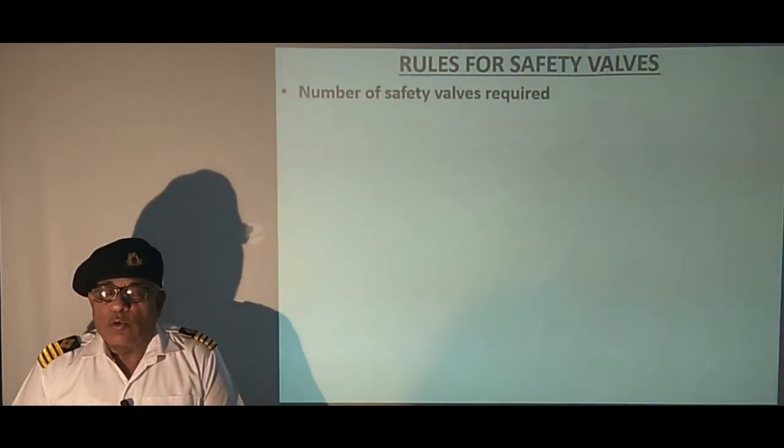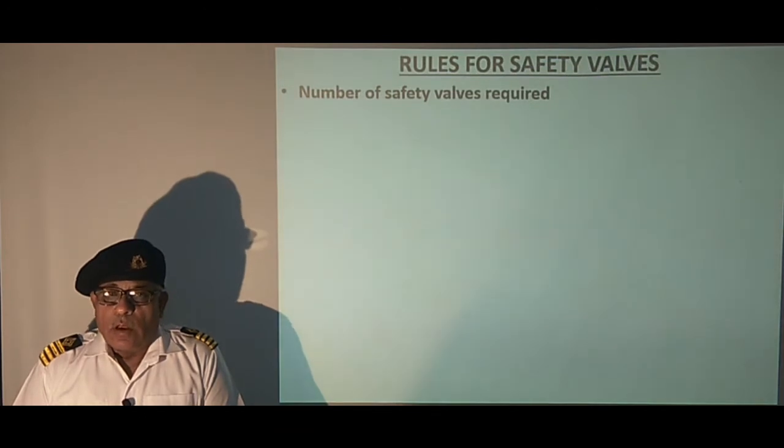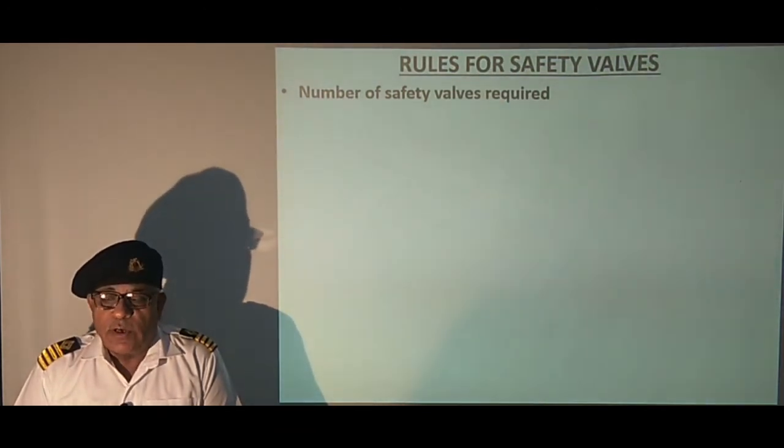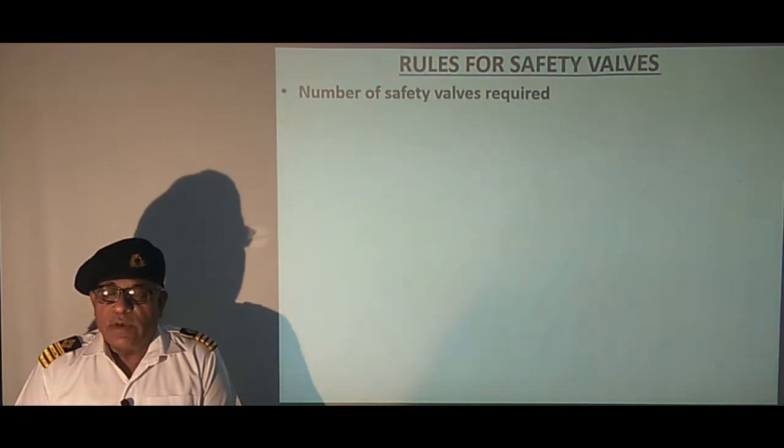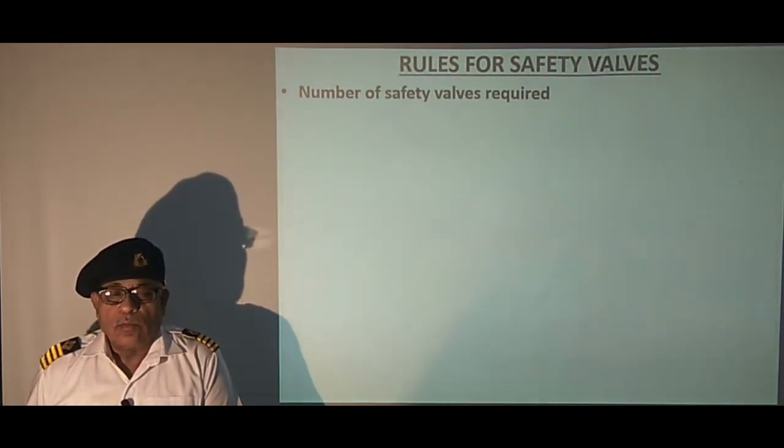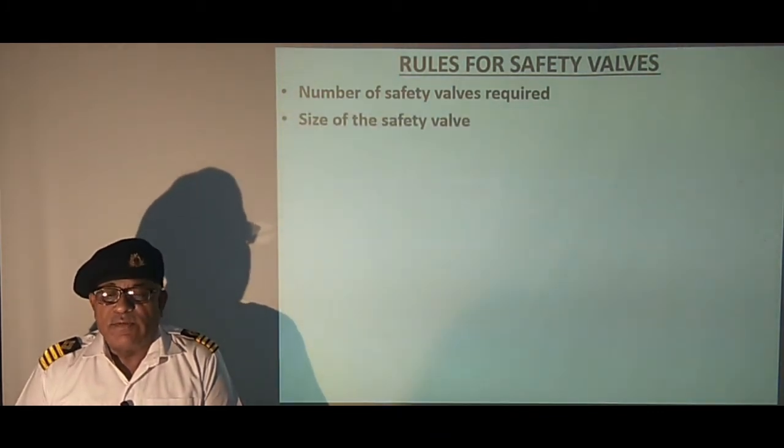Number of safety valves required. Regulation requires that at least 2 safety valves should be fitted on the steam drum. If the boiler is equipped with a superheater, a third safety valve should be fitted on its outlet header. Next is the size of the safety valve.